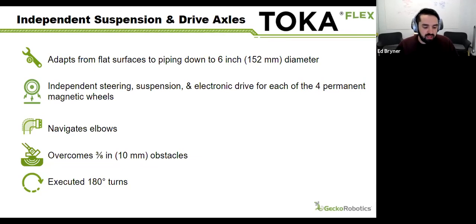Yeah, absolutely. So there's a couple key components that are built into our system. We actually have some tires that are attached to our magnetic system to protect your coatings first. Obviously, those are there with intention and reason. And ultimately, much like all other ultrasonic systems, we do use an immersion-based technique to be able to capture our ultrasonic data. But generally, we deal with coatings much like many other ultrasonic techniques. The better the coating is coupled to the surface, the better your data is going to be. And depending on that coating, if you do have concerns over your particular coating, we have extensive subject matter experts and people in-house in lab that we can take your samples and actually be able to test those in-house prior to coming out to site to verify that your coating is not going to interfere with the reliability and robustness of our inspection as well.